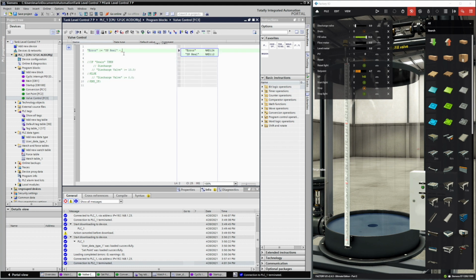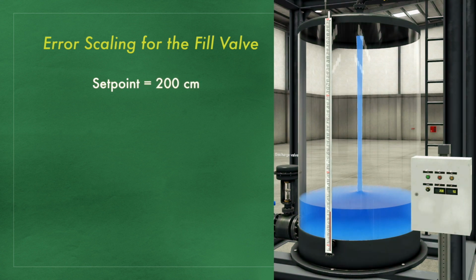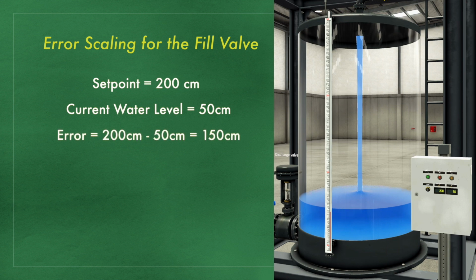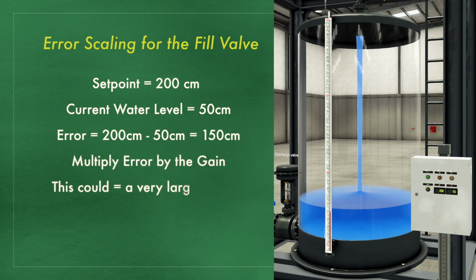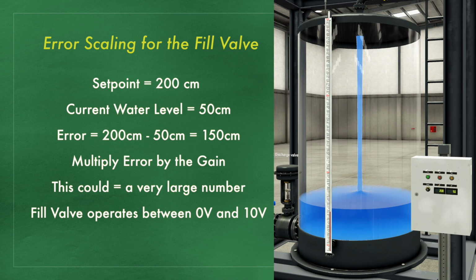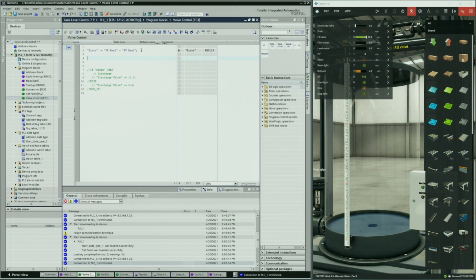However, this figure is based on the tank actual values. For example, if the set point is 200 centimeters and the level is currently 50 centimeters, then the error would be 150 centimeters. And if you multiply 150 by the gain, this would be a very large number. This number is then used to open the fill valve, but the fill valve only goes from 0 to 10 volts. Therefore, we need to normalize the error, then scale it between 0 and 10 volts. And the way we do that is by using the NormX and ScaleX conversion operations. So let's enter the code for the conversion operations now and explain it as we go along.